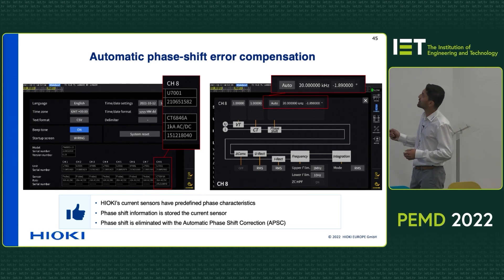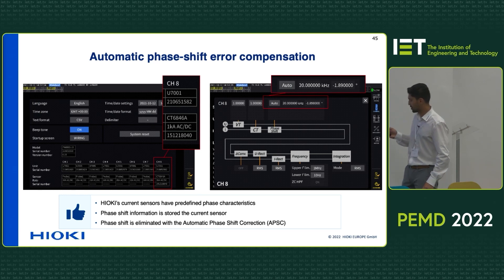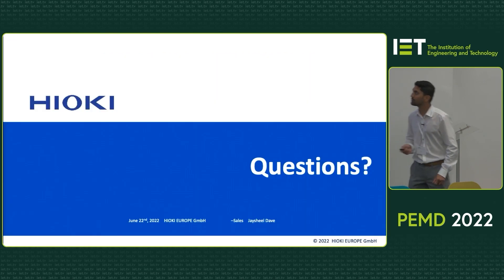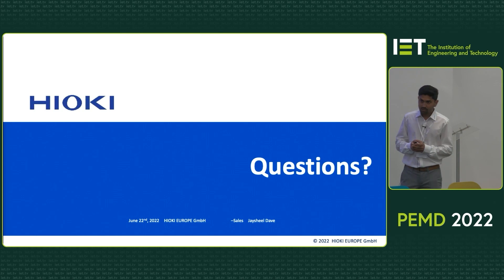For example, when a CT is connected and the power analyzer knows that at 20 kilohertz the phase delay is 1.89 degrees, the power analyzer reads it directly and compensates it automatically. Thank you for your attention — if you have any questions, you can ask me.